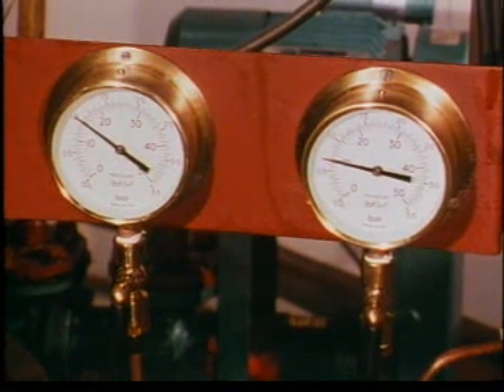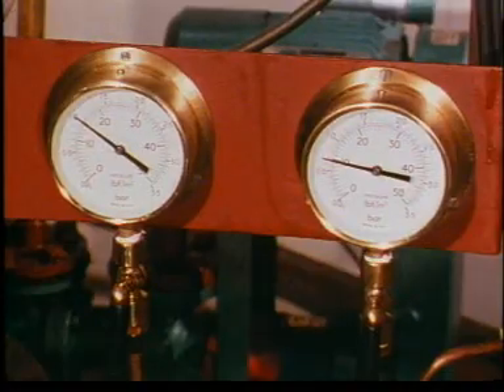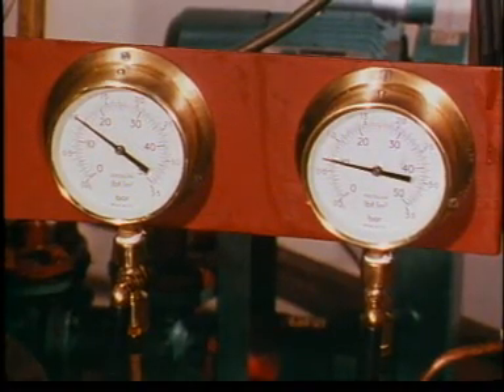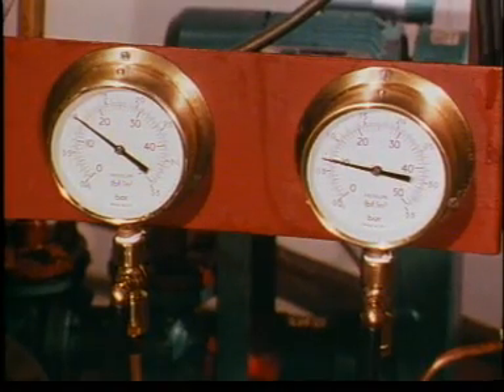Two pressure gauges are fitted, one reading pressure before and one after the coalescing elements. The first should read only slightly lower than the pressure in the separator, allowing for frictional losses in the intervening valves and pipework.